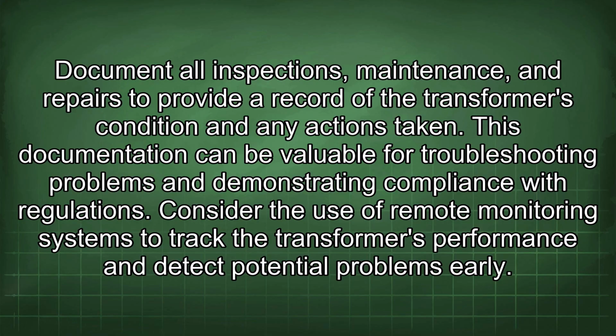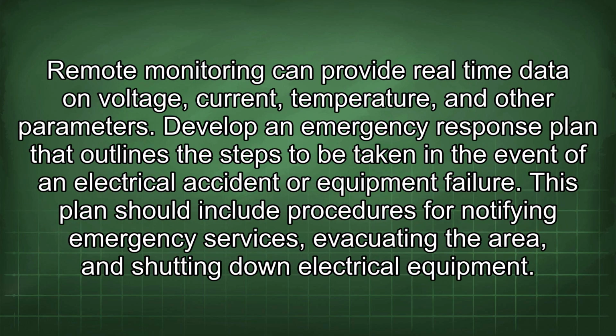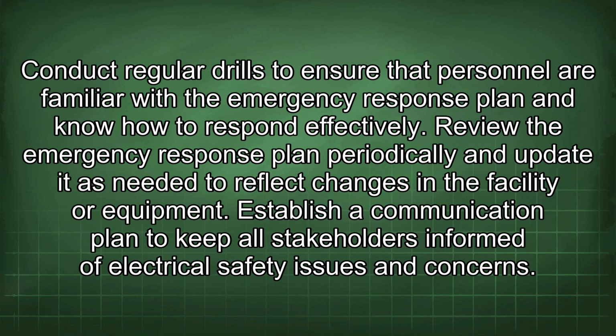Consider the use of remote monitoring systems to track the transformer's performance and detect potential problems early. Remote monitoring can provide real-time data on voltage, current, temperature, and other parameters. Develop an emergency response plan that outlines the steps to be taken in the event of an electrical accident or equipment failure. This plan should include procedures for notifying emergency services, evacuating the area, and shutting down electrical equipment. Conduct regular drills to ensure that personnel are familiar with the emergency response plan and know how to respond effectively. Review the emergency response plan periodically and update it as needed to reflect changes in the facility or equipment.